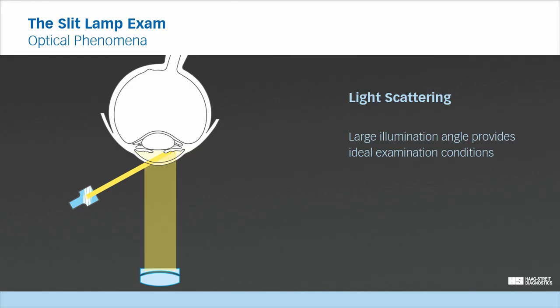Light scattering can best be observed when a large illumination angle is used. With a small illumination angle, the field where you can observe light scattering is restricted. Therefore, in most cases, you will create light scattering with an illumination angle of greater than 45 degrees.